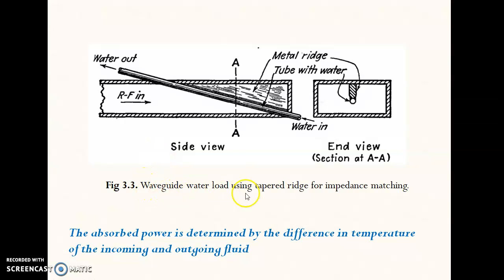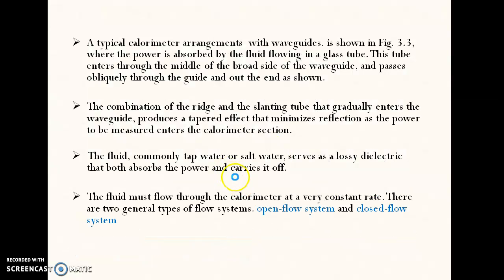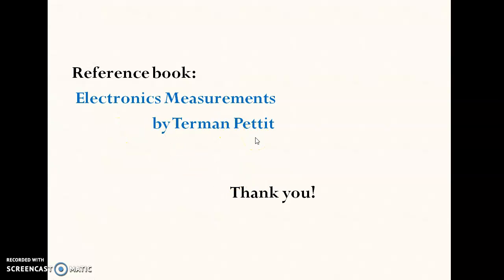Another arrangement of the calorimeter method is in a waveguide. One tube has been used where the fluid will flow, and the RF input power — the same principle will be used here also — the fluid in the tube will absorb the power and we can measure the temperature difference of the water in and the water out in this section as well. This arrangement is actually for a waveguide, not for a coaxial cable. You can refer to this book for further details. Thank you, and we will meet for another lecture.